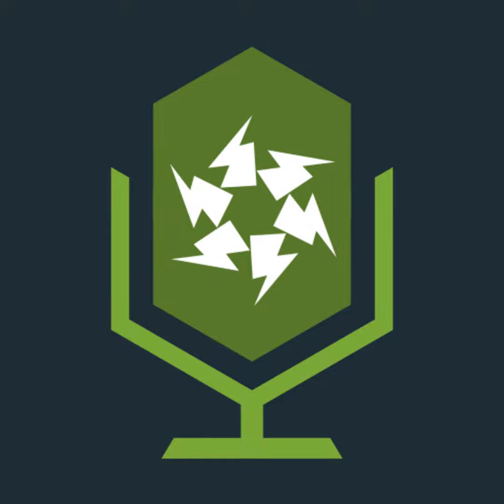But then this is one that's on all the Facebook groups. Do Type 3 multi-gang extension leads need to be part of the same manufacturer as Type 1 and 2? And how many times have we seen on Facebook groups where Sparks go, oh, I don't know, do I install it? What do I do? And then you get some more and go, yeah, just get a load of Type 3 surge protection extension leads, job done, it's covered. Yeah. Please don't use those.